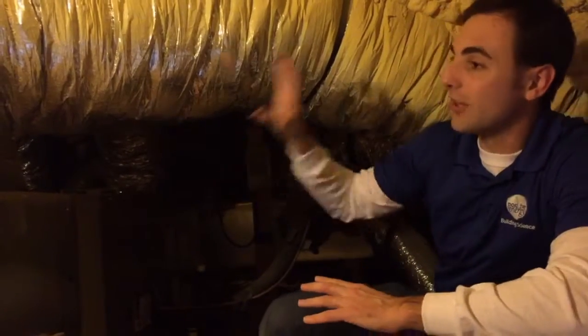So we're back in the attic now, talking about common airflow problems. Things that contribute to poor airflow could be high static pressure, not getting enough return air, causing your fan to work harder and suck through. Imagine trying to run a marathon only sucking through a coffee straw. You're not going to get much air, and therefore you're not going to get much performance either. So you want to look at the return sizing. You want to make sure that there are no major kinks in any ducts on the supply side or the return side that are going to inhibit the air from getting through.